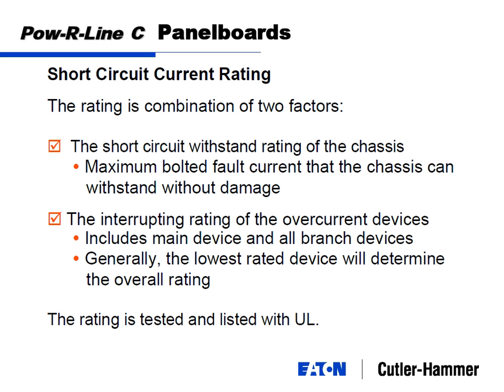When we talk interrupting rating, it's the ability of the circuit breaker itself to open and interrupt the flow of current at 65,000 amps. So I can tell you this breaker here is rated for 65,000 amp short circuit rating, and that means it can interrupt 65,000 amps. So if 65,000 amps is flowing through this small circuit breaker, the contacts on this side of the breaker are going to be able to open up and break that current.